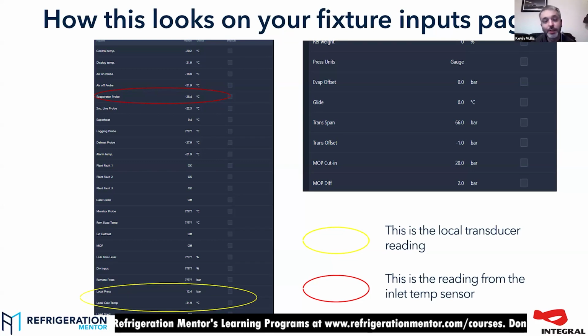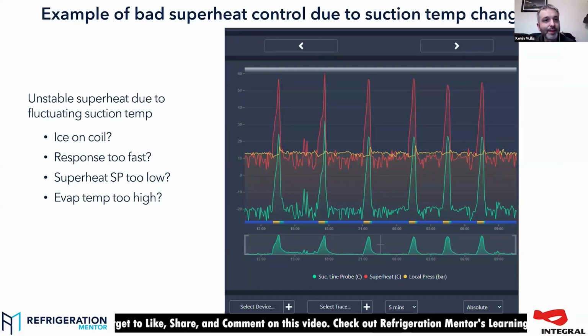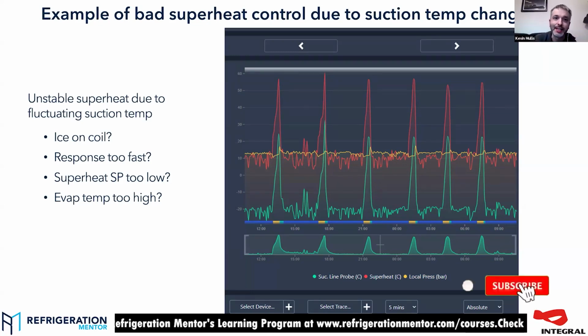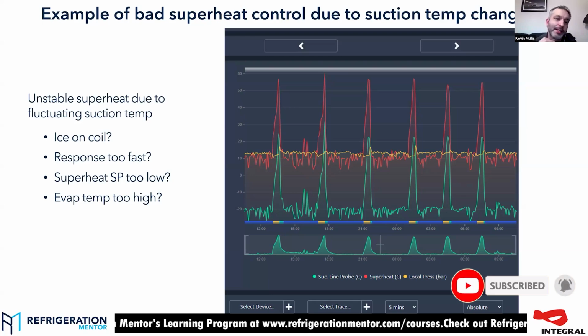What we used to do for cost, and because it was a decent enough approximation, was put a probe at the inlet of the coil, because just when you get out of the expansion valve and you get into the evaporator, you haven't really absorbed any heat yet. You're almost certainly going to have liquid and vapor there. So you're going to have a saturated condition, which means at that point, you should see what the evaporating temperature of the gas is. It's a decent approximation of doing it, but it's vulnerable for all the reasons I said, to you not putting the probe in the right place, or if you do put the probe in the right, inverted commas, place, whether it actually sees any liquid. If it's not seeing liquid, you're not going to see the evaporating temperature.